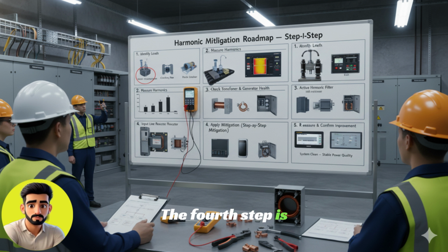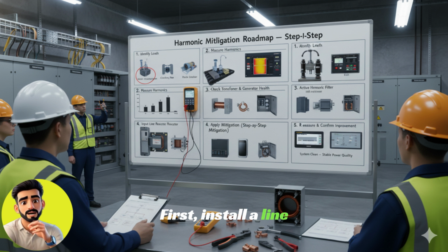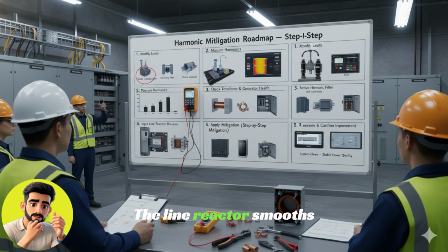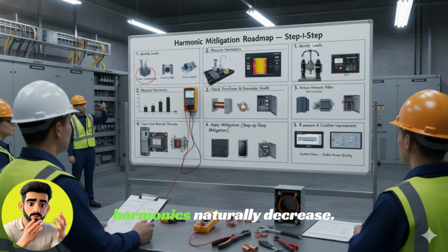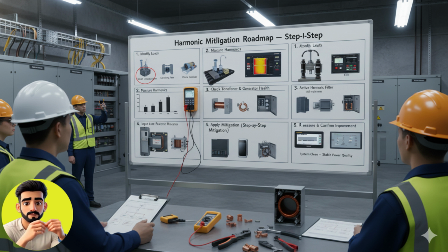The fourth step is to apply mitigation step by step, starting from basic measures. First, install a line reactor. The line reactor smooths the input current and harmonics naturally decrease. Then, install a DC choke. This stabilizes the DC bus and reduces rectifier distortion.